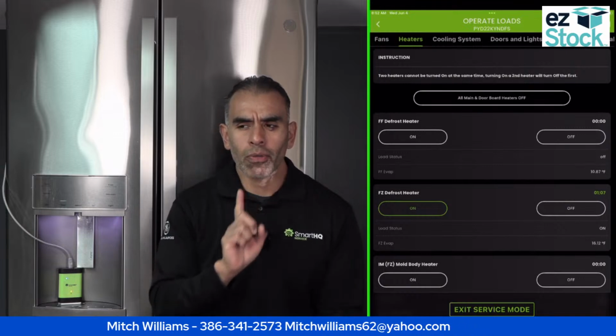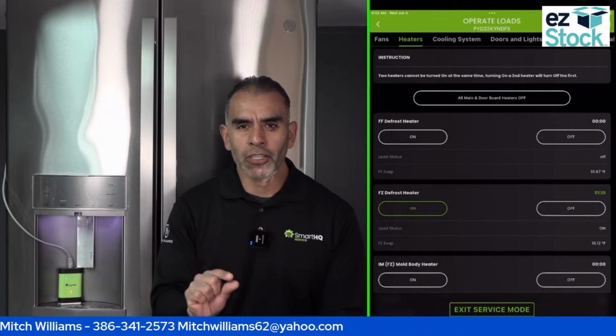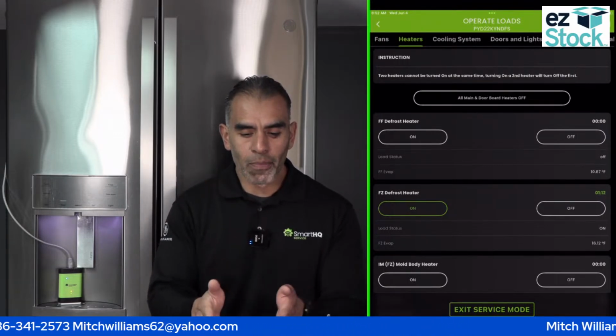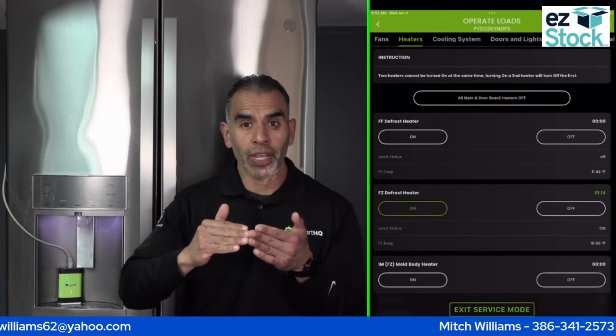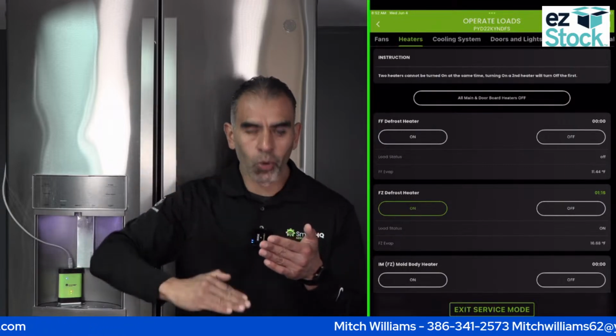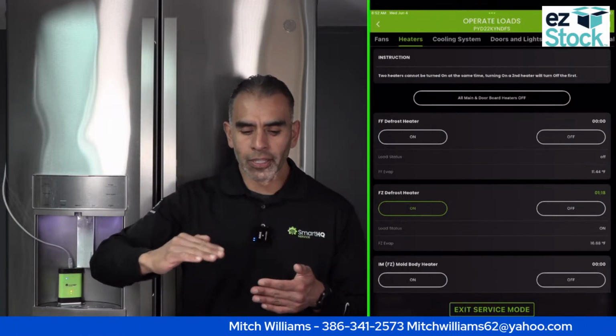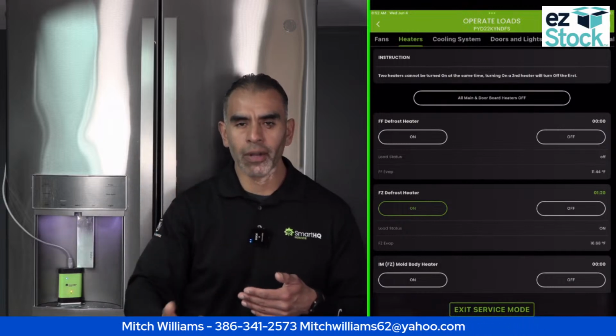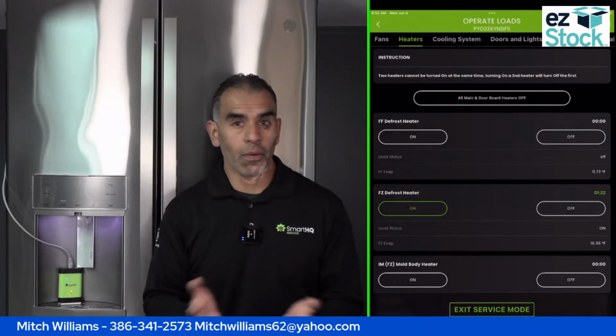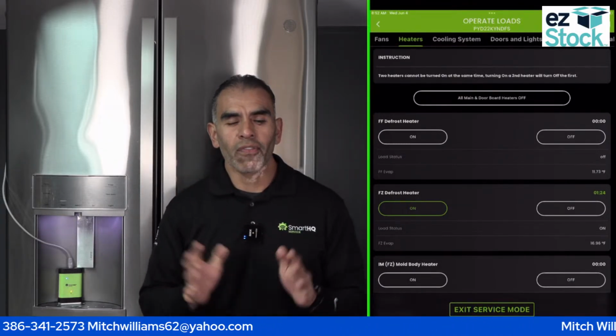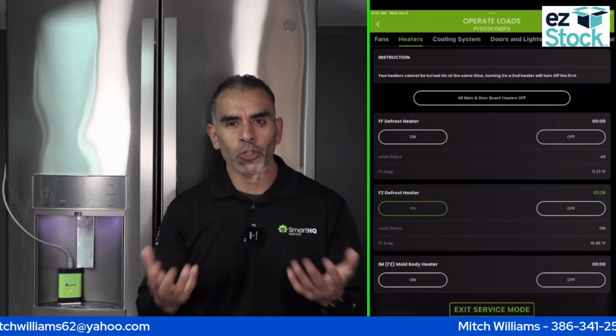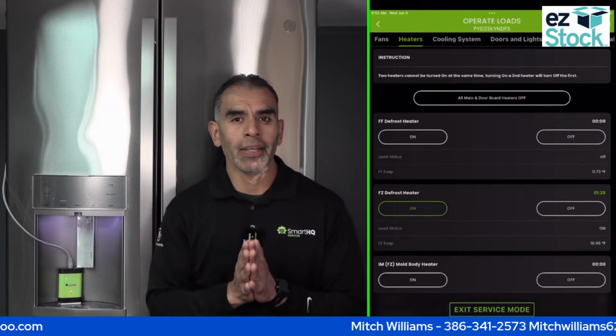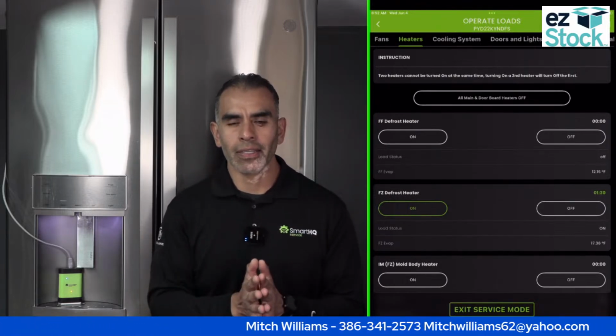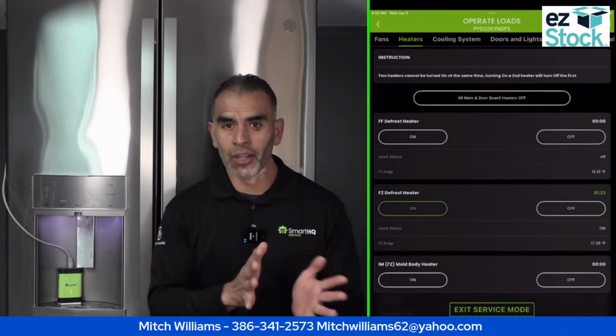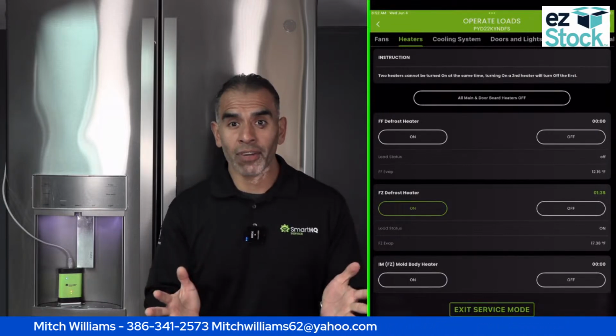Something I didn't mention: the evaporator thermistor could be bad. The fact that it read the temperature going down when we cooled the unit, and now will go up when we turn on the heater, tells us the thermistor is working well. If it was bad, open or shorted, you'd see that in red, but in this case it appears good. That's another component you can check without taking out a single tool.